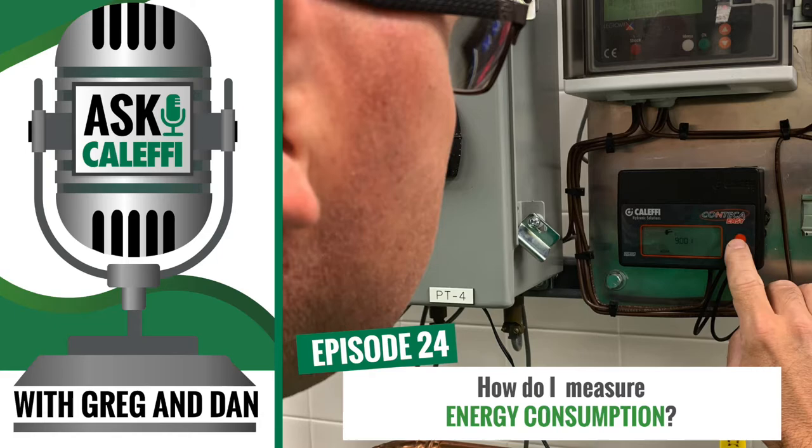It also comes with a flow meter, and we have varying sizes to measure different flow rates — essentially different CVs. We have a single-jet flow meter in half-inch, three-quarter, and one-inch. Then the multi-jet from one inch all the way up to inch-and-a-half. We also have the unit available up to eight-inch flanged for large commercial applications. The sensors come factory-wired into the control.